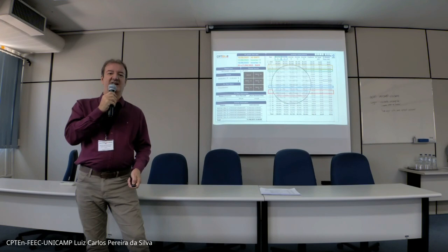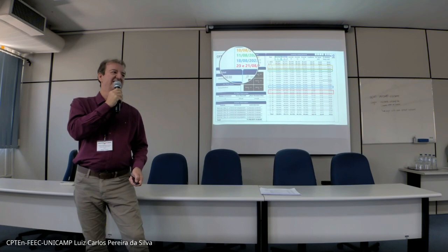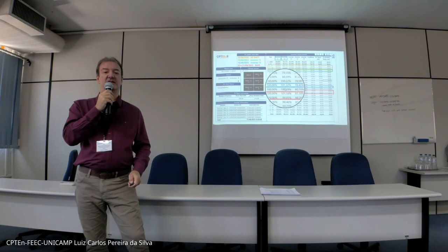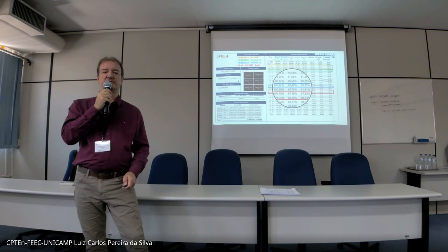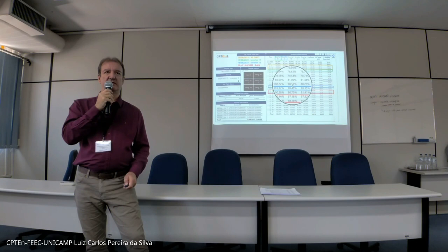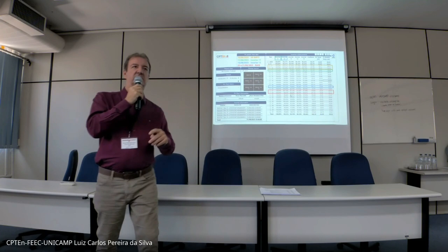And then, sadly, it started to rain. So our experiment was aborted because every panel was cleaned by nature. But it gave us another insight. From 21 and 22 of August, you can see the difference between 78% and 88%. What we can say: before rain, 78%. After rain, 88%. So the rain increases the generation capability by 10%.